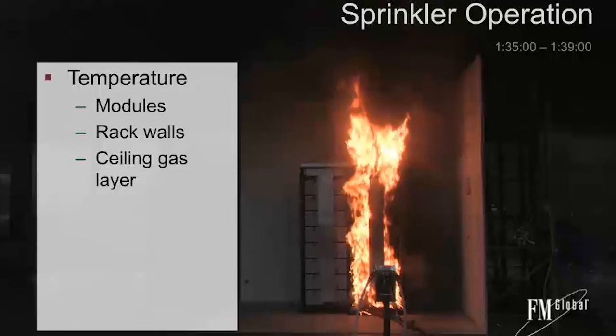In terms of temperatures, we're measuring the temperature of each module, as well as the rack walls. That's the metal surrounding all the modules. And this is conducted in a large burn lab. So we also have 125 thermocouples at our ceiling, and velocity measurements, and we're measuring heat flux surrounding the whole storage system. So in total, there's around 300 different instruments measuring during this test.